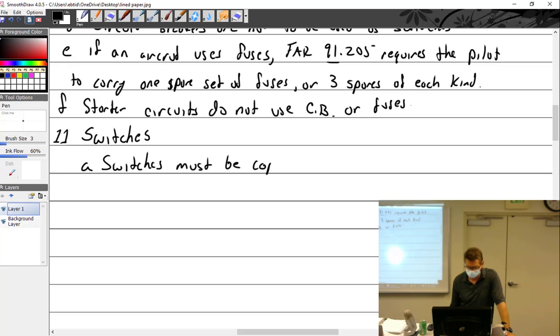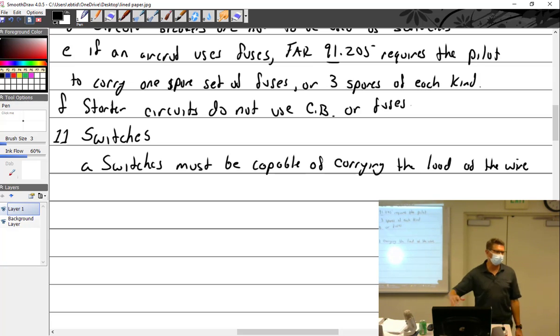Switches must be capable of carrying the load of the wire. It makes no sense to do all this work figuring out we're using, say, a number 20 wire with a 5 amp fuse of a certain length, and then put in a little tiny switch that gets so hot when you turn it off you practically need oven mitts and a placard saying so. That means too much current is going through the switch. You can't do that — you have to match the switch to the load.